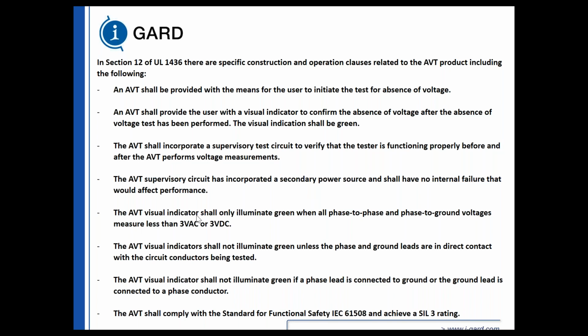The absence of voltage indicator shall only illuminate green when all phase-to-phase and phase-to-ground are less than 3 volts AC or 3 volts DC, depending on whether it's AC or DC, and we do that. The visual indicator shall not illuminate green unless the phase-to-ground leads are directly in contact with the circuit conductors being tested. This is done through the continuity test, and we perform that test twice with the i-Gard absence of voltage tester. It shall not illuminate green if the phases are connected to ground and the ground leads are connected to the phase conductors. Okay, so if you swap the ground and the phase conductors, it's not going to illuminate green.